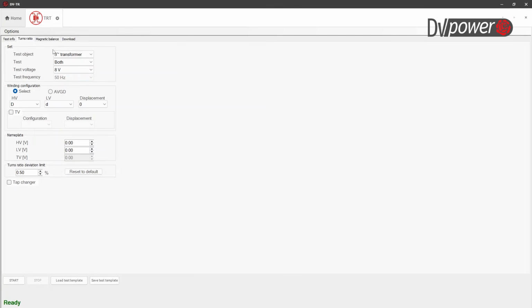We need to insert data about test object, which is 3-phase transformer. We select if we want to perform sequential, simultaneous, or both tests, which we will perform now. Test voltage can be selected between these values. With some of other TRT devices from standard series, it can be selected up to 250 volts, but with TRT 33C, these are selectable test voltages, and for this transformer 8 volts should be enough.